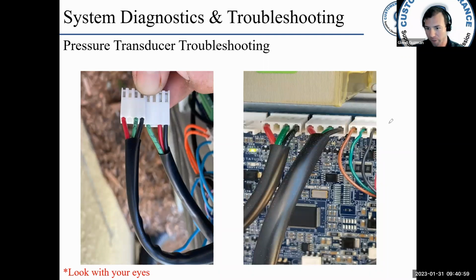If you look at the picture on the right, this is how the transducer should be wired from left to right: red, green, and black. Okay, red, green, and black. The one on the left, you can see there's a difference. We have red, green, and black, and then green, red, black. Okay. This particular issue, the unit ran for almost a year before the issue was caught.